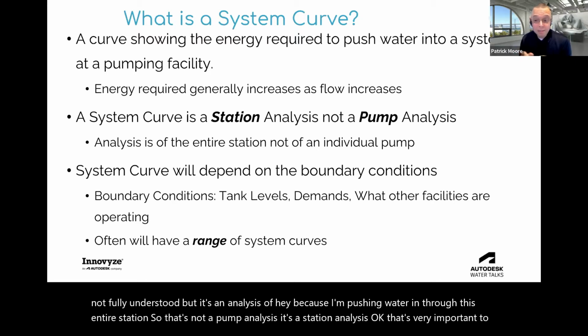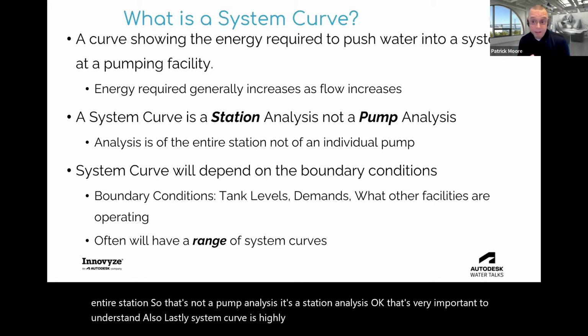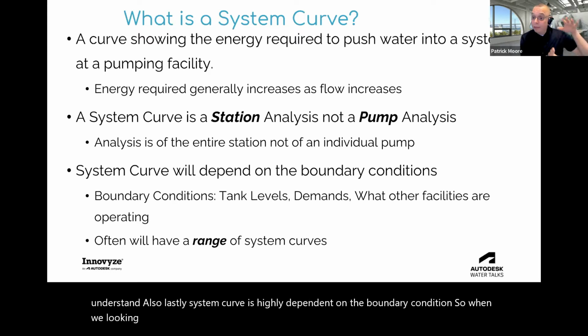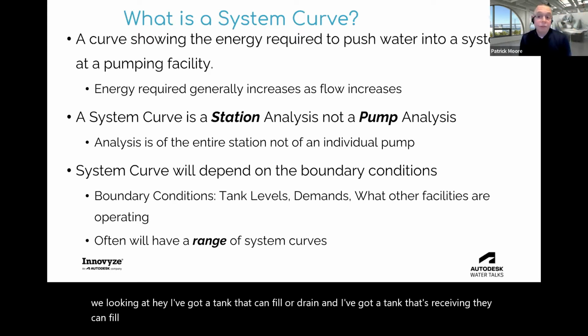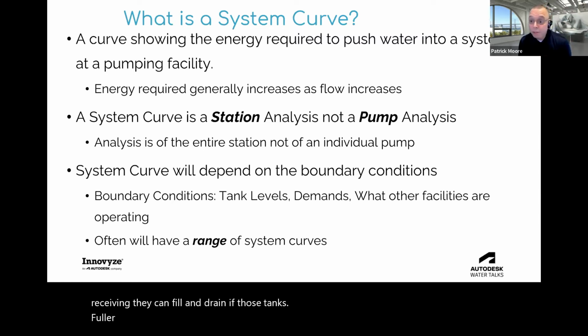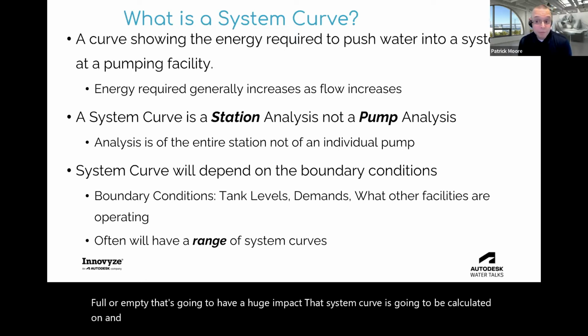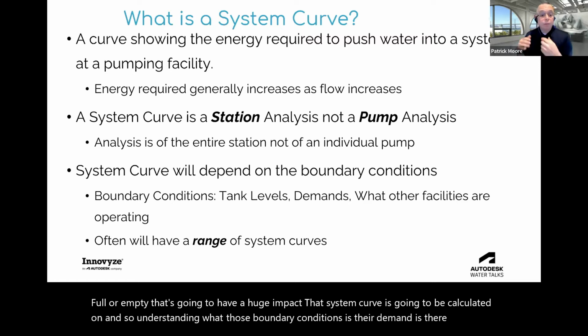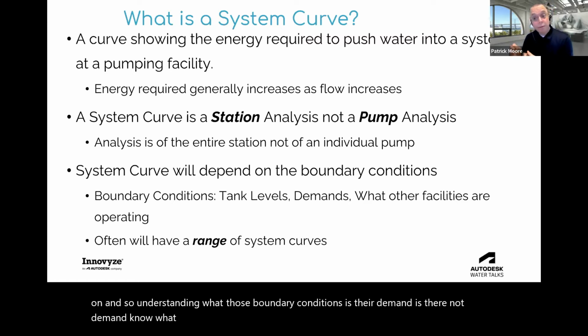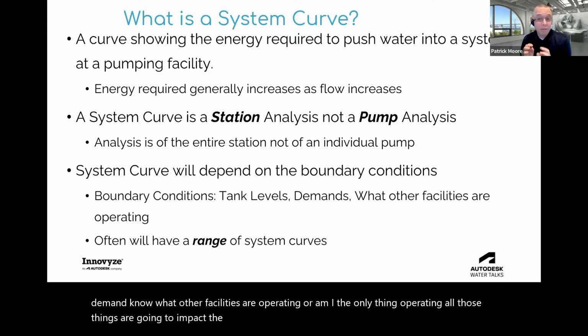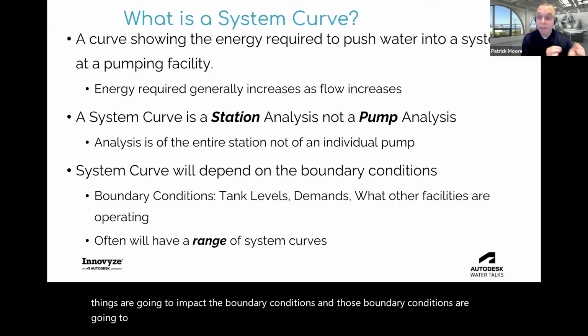Also, lastly, a system curve is highly dependent on the boundary conditions. So when we're looking at, I've got a tank that can fill or drain, and I've got a tank that's receiving that can fill and drain, if those tanks are full or empty, that's going to have a huge impact on what that system curve is going to be calculated on. And so understanding what those boundary conditions are: is there demand? Is there not demand? What other facilities are operating, or am I the only thing operating? All those things are going to impact the boundary conditions, and those boundary conditions are going to impact what is going to happen in this analysis.